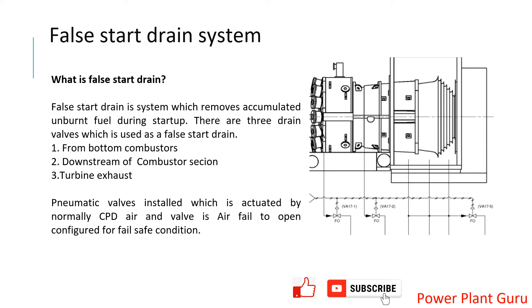Now you can see there are three drains — let me put the pointer. There is one drain from the bottom of the combustion section, another drain from the downstream of the combustion section at the lowest point, and a turbine exhaust drain. All those drains come out to atmosphere, and the operator has the opportunity to check whether sufficient air is coming from them. If started on liquid fuel, some liquid should also come out if there was no flame or if the flame initially came but was not stabilized.